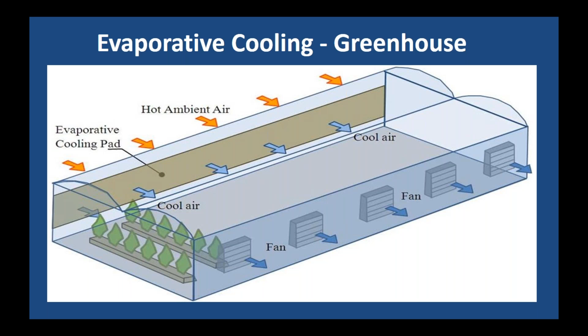Altogether, these aspects shown here, for a well-designed and operated indoor grow, can save up to 40% per gram of flower compared to a standard indoor grow—pretty significant savings potential. And at least in Colorado, a well-designed and operated greenhouse can save 60 to 70% of the energy compared to a standard indoor grow. That's because greenhouses can use sunlight and take advantage of evaporative cooling, which is much more efficient than refrigerant-based cooling.